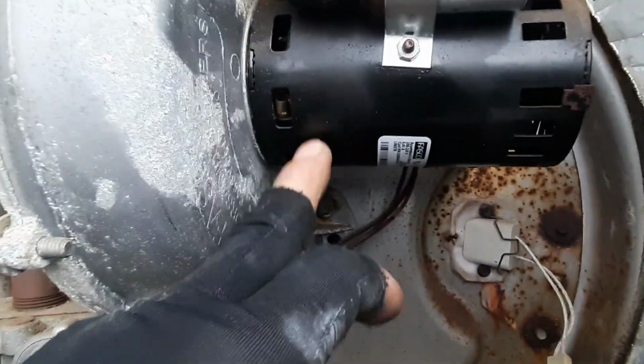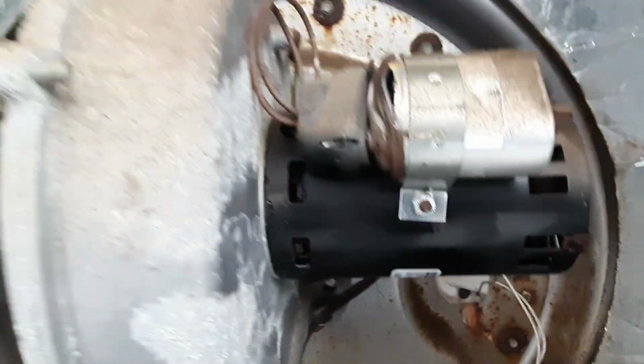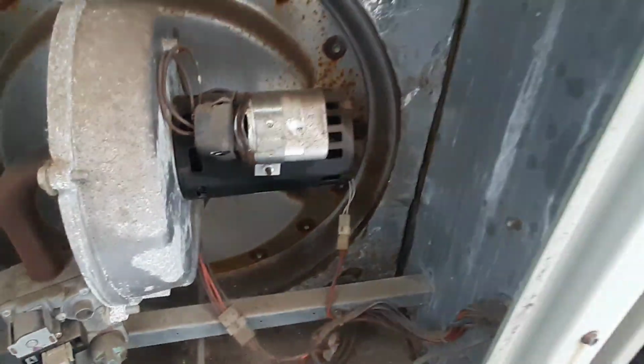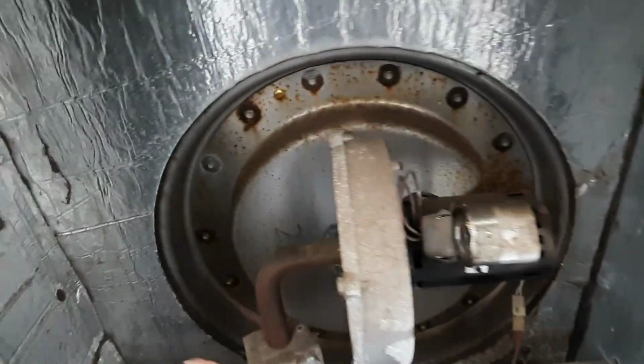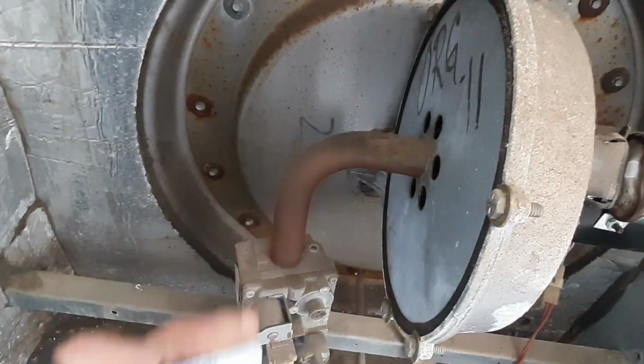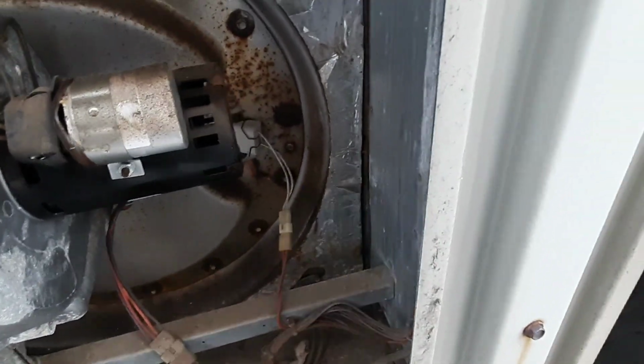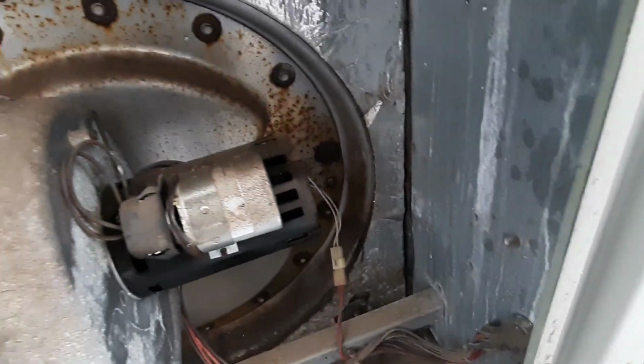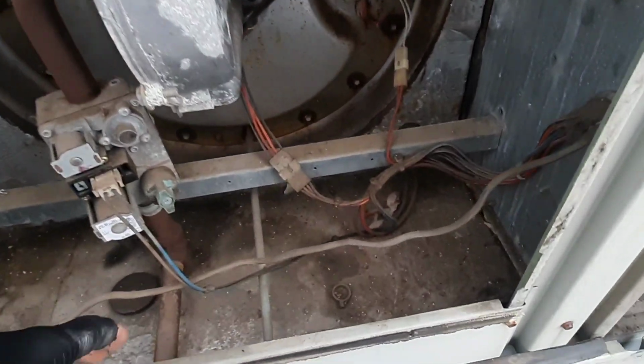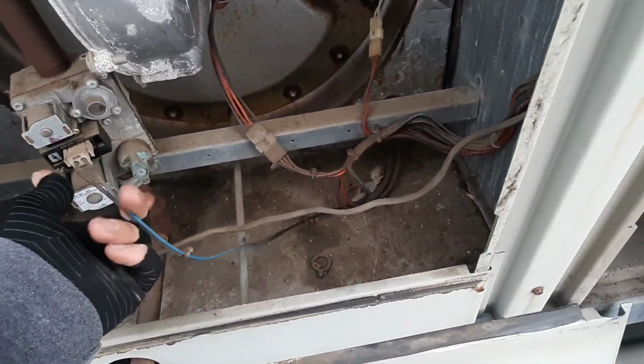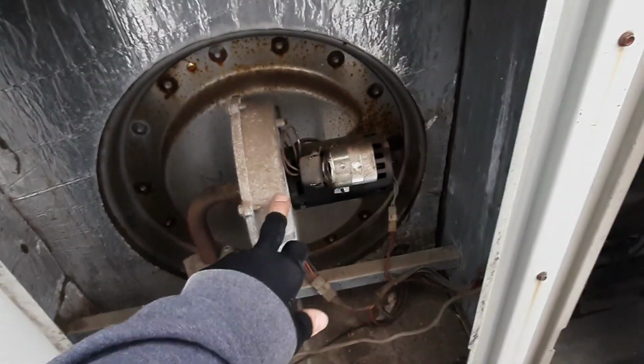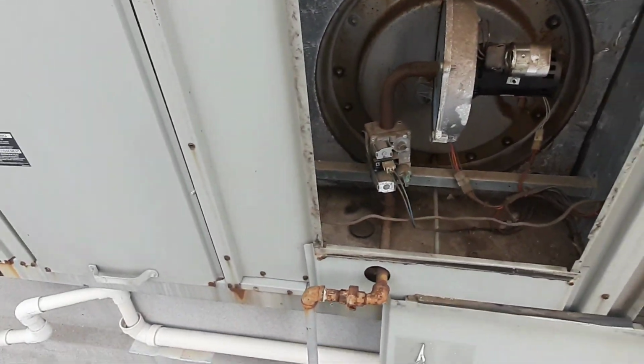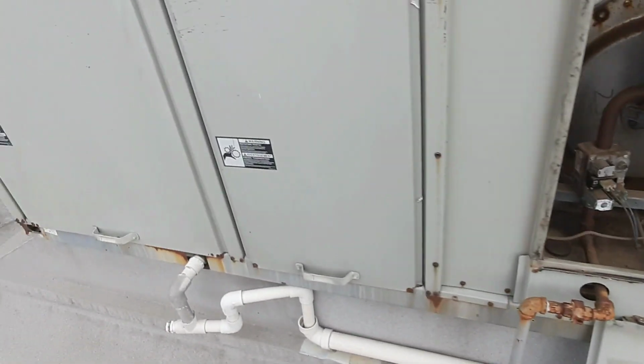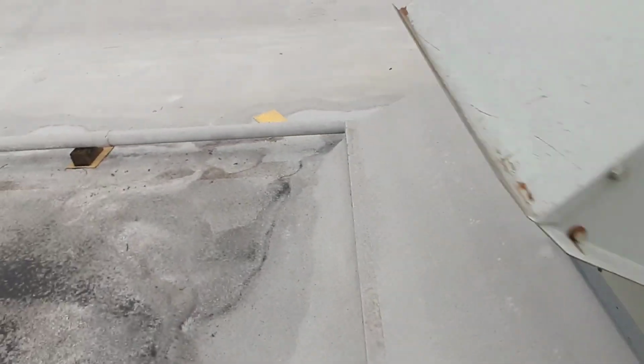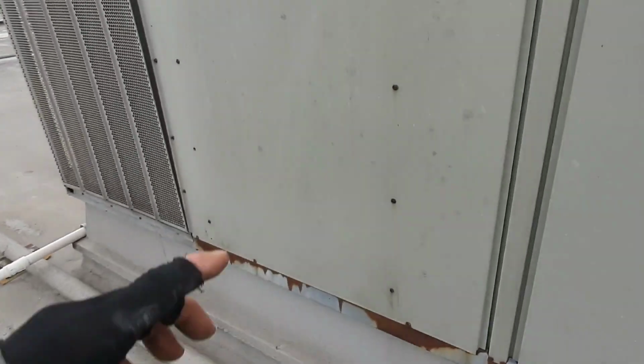So we got an inducer motor burnt up. We got a bad capacitor, obviously. It still spins. It ain't gonna spin with the new capacitor. I can smell it. That's probably what my lockout was, the heat lockout. We'll get in and look at the blower. I can't explain that stuff. I've never seen one go off and on like that constantly.